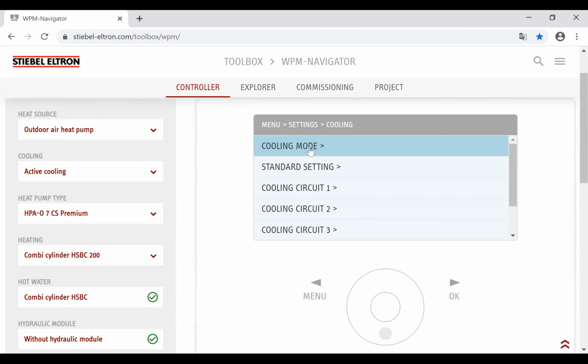Now, you'll note, with cooling, we have two options for how we want to cool a particular circuit. And we can turn cooling on and off per circuit. So if you've got a job where you've got upstairs radiators, two sections of underfloor heating, and fan coil units, you're going to have 4 circuits, obviously. So we can look at circuit by circuit. You can say circuit number 1 will be the radiators. Let's turn cooling off on the radiators. We don't need cooling on the radiators. They're not there to cool. Circuit 2, however, could be our underfloor main living area. So let's turn it on.